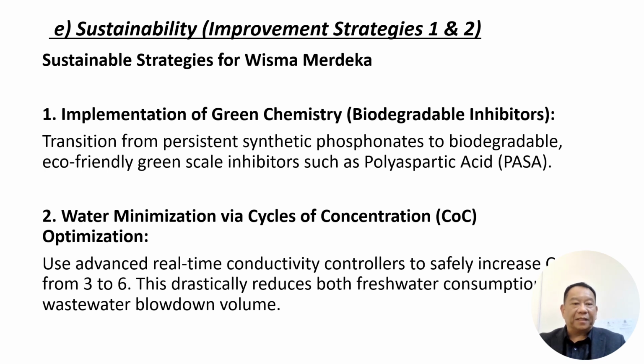Okay, so implementation of green chemistry, biodegradable inhibitors: transition from persistent chemicals to the green scale inhibitor such as polyaspartic acid, or they call it PASP. Water management via cycles of concentration (COC) optimization, using advanced real-time conductivity control to safely increase from 3 to 6, which drastically reduces both freshwater consumption and wastewater blowdown volume.